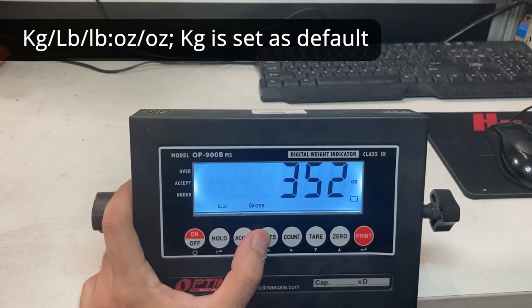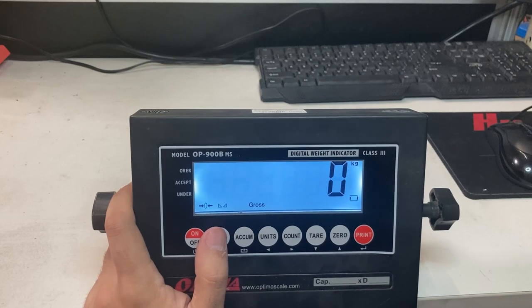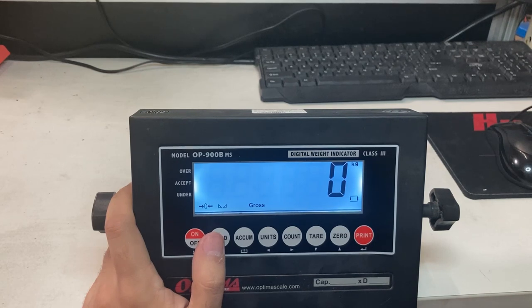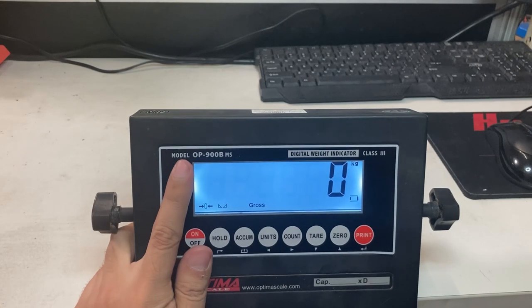Go down. So if you want to do grams, you have to do grams only. There's no option for, say, kilograms, grams. It has to be kilograms, pounds, kilogram, pound, ounces, whatever you're looking for. But that's how you enable grams and ounces in the OP900B model.